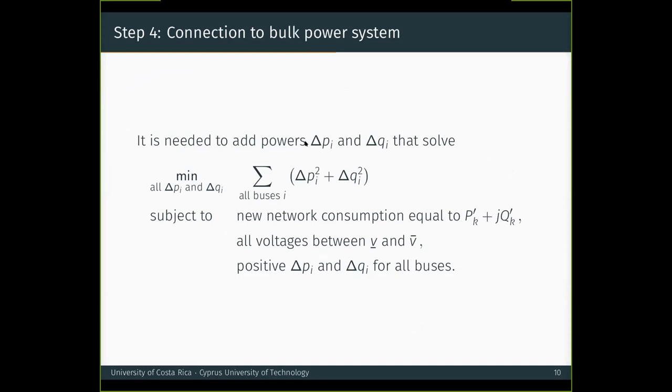To do that, we formulate the problem as follows. It is needed to add powers Δp_i and Δq_i that minimize some metric of the difference of those allocations. To illustrate, we employ the sum of the squares. And also this optimization problem must be subject to the new network consumption being equal to the one I showed in the previous slide, while the primary operates at the real voltage of the medium voltage network. Also that all voltages lie between some bounds to ensure either a diverse or a flat voltage profile, and finally, that all of those small loads are positive. In other words, this modification of the networks can be thought of as an optimal power flow problem. But instead of minimizing generation costs or losses, we minimize deviation from the allocation, which we designed in order to be realistic.